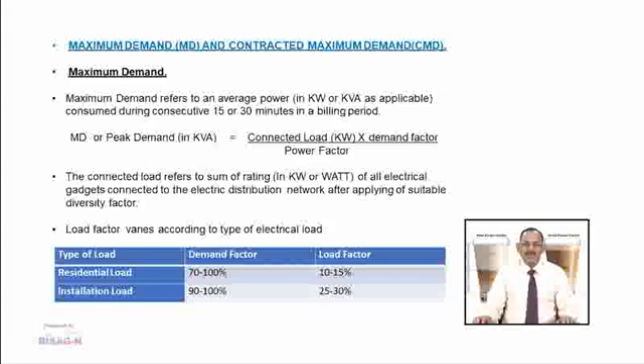Maximum demand or peak demand in kVA equals connected load in kW multiplied by demand factor, divided by power factor. The connected load refers to the sum of ratings in kW or watt of all electrical gadgets connected to the electric distribution network after applying suitable diversity factors. The load factor varies according to the type of electrical loads.